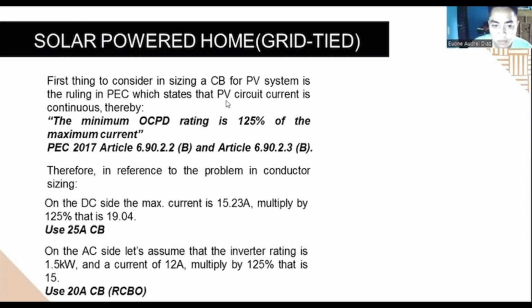which state that PV circuit current is the continuous thereby. The minimum OCPD, ang OCPD daw po is overcurrent protection devices. Rating is 125% of the maximum current or PEC 2017 Article 6.90.2.2b and Article 6.90.2.3b. Therefore, in the reference to the problem is in conductor sizing.